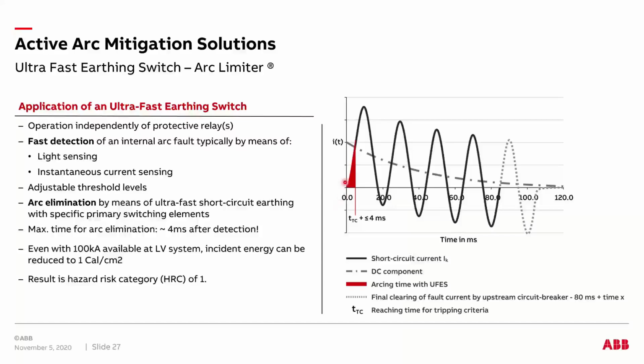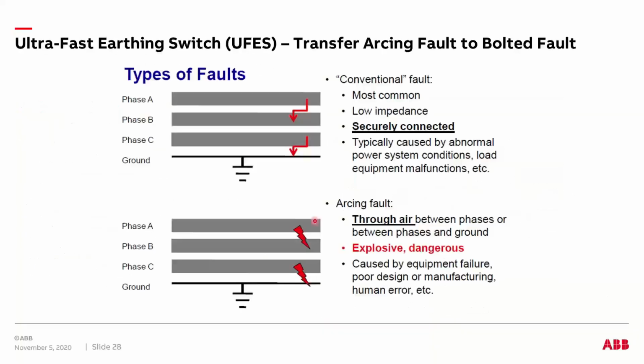So within about 4.5 milliseconds, you are converting that arc flash incident into a bolted fault, whereby the incident energy that is being developed inside your switchgear is limited to less than 1.2 calories per centimeter square, which is effectively like a category 1 HRC, right? And so that's the key differentiation of this equipment, where it does not let the arc flash develop within your switchgear beyond 4 to 5 milliseconds.